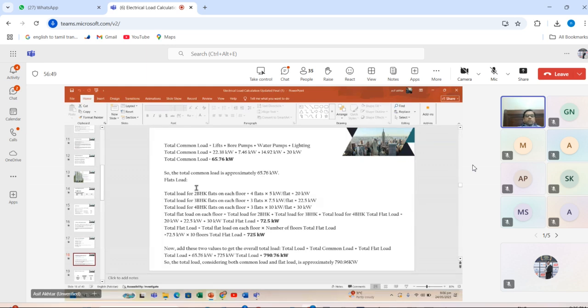Okay, so now the total load for 2 BHK flats on each floor. In the previous slide I told you that for 2 BHK flats the electricity meter we have provided is 5 kilowatt. The number of flats on each floor is 4. So we multiply 4 flats by 5 kilowatt, which is equal to 20 kilowatt. Okay. Now the total load for 3 BHK flats on each floor: 3 flats multiplied by 7.5 kilowatt is equal to 22.5 kilowatts.